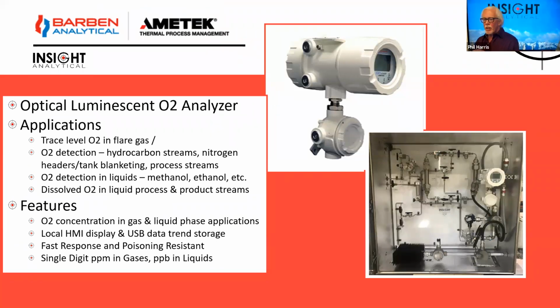Again, another AMETEK product that we work with is the Barben Analytical oxygen analyzers. These are a quench fluorescence or an optical luminescence type oxygen analyzers. Again, you see this trend of us looking towards spectroscopic things. It allows us to make an oxygen measurement, again, with no moving parts, and it doesn't really have to chemically interact, if you like, in the same way as a lot of sensors do, like an electrochemical cell or anything like that, to make oxygen measurements. Very sensitive, down to parts per billion levels in liquids.